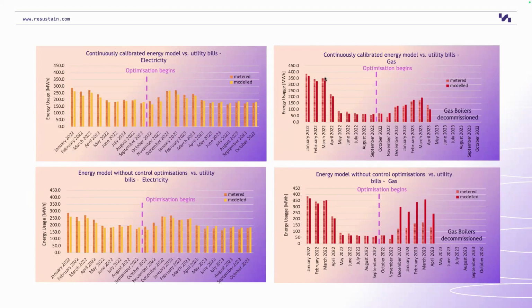Same here. This is electricity. This is gas. So you can see it's fairly well controlled in the model. A couple of hiccups maybe as we first began, but it's not a bad calibration. Now, to see how much impact the control changes have had, we can use the calibrated model and take those control changes off and run it through for the weather data of that time with what's going on in the building, and then we can see what impact those control changes have had.